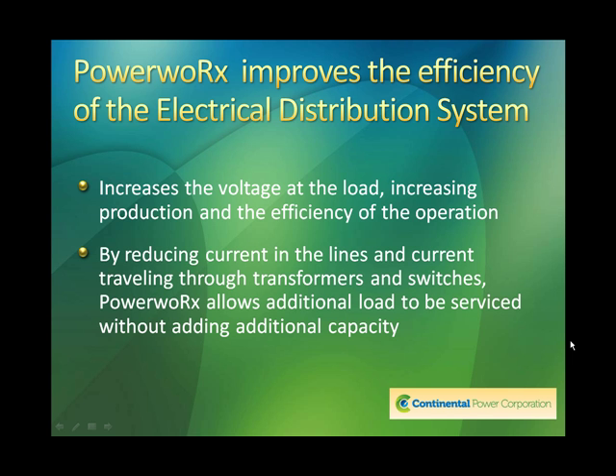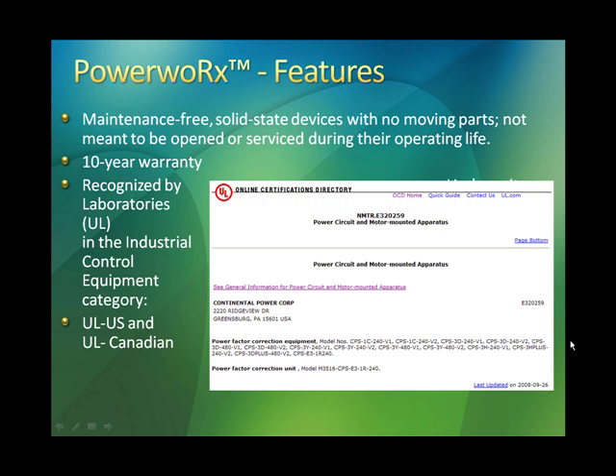Where there is a poor power factor, we can reduce the current significantly, freeing up the kVA that is needed coming from that transformer. So this is one of the big benefits of the PowerwoRx system. Some general information I want to share with you. These are maintenance-free products. They're solid-state devices. There's no moving parts. It's not meant to be opened. It's not needed to be opened or serviced during the operating life.